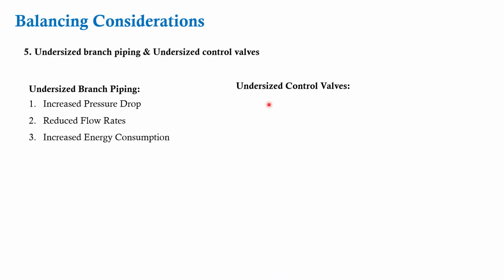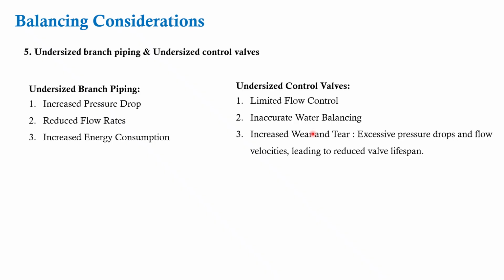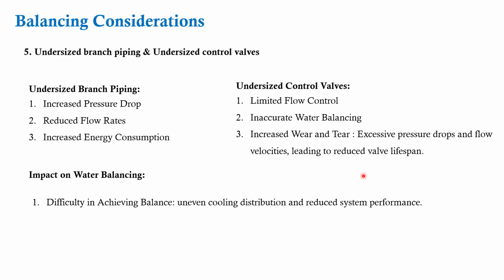Talking about control valves, if they are undersized, how is it going to impact my system performance? It's going to limit the flow control. It's not going to deliver the given flow requirement for the efficient performance of the air handling unit or the fan coil unit. There is going to be inadequate water balancing in the system, which adds more wear and tear, and excessive pressure drop and flow velocities lead to a reduced life span of the valve. So I need to ensure that. So what is the impact on water balancing because of undersized branches and control valves?